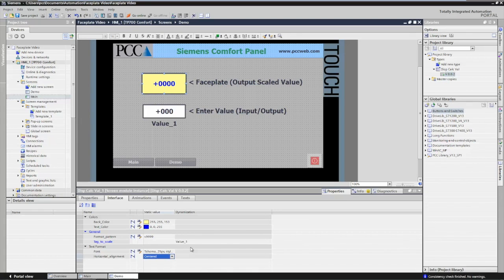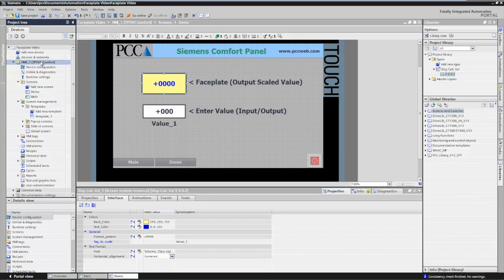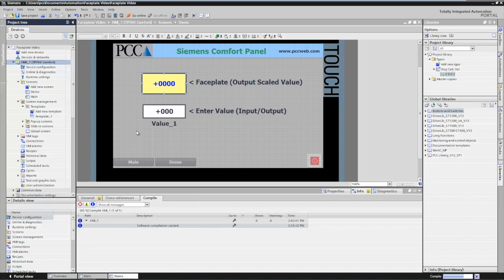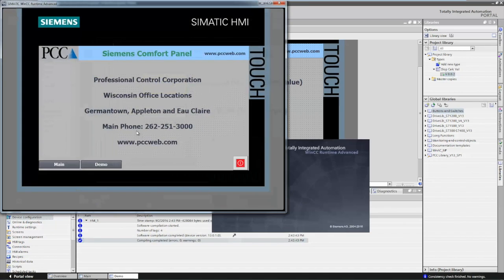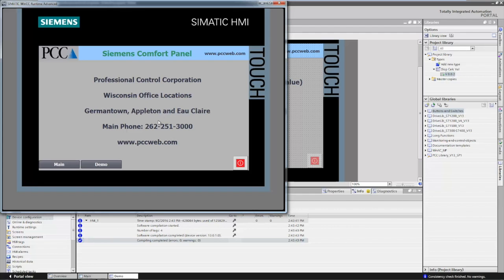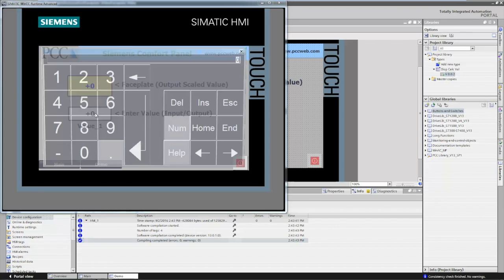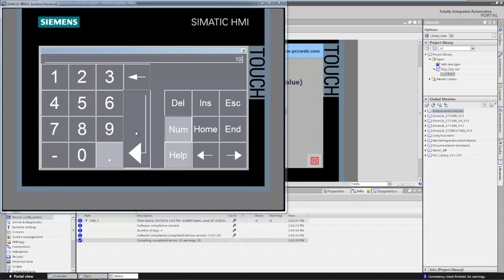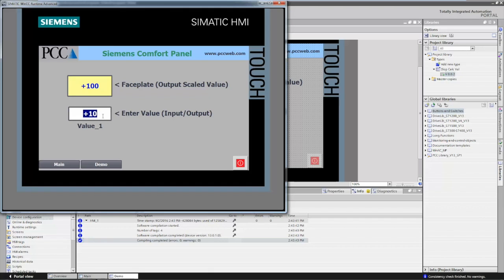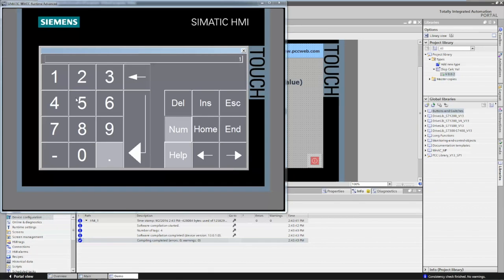Now I'll highlight my HMI and start the runtime simulator. This will compile my project and start the runtime. Here's my default application screen — I'll go to the demo screen, and when I enter a value of 10, it takes 10 times 10 and I get 100. If I put in a value of 1, it takes 1 times 10 and gives me a value of 10. This is how you create a basic faceplate for scaling a value in the WinCC Comfort software.